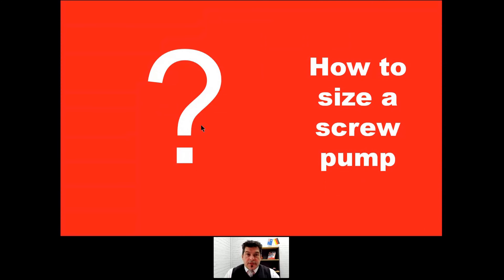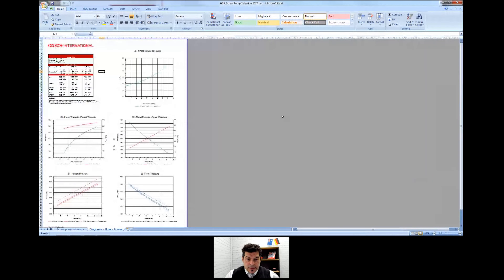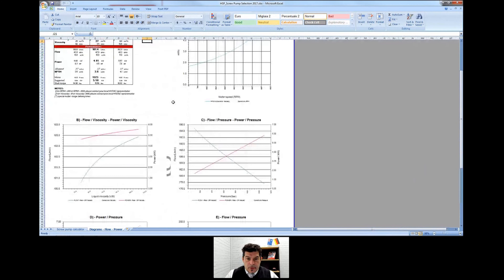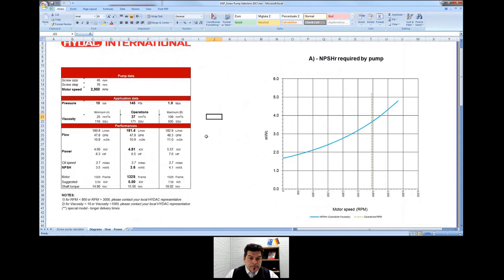How do you size it? In HYDAC, we have nice software. We give the customer a PDF with all the data characterizing the pump. The first chart — the most important one — shows the Net Positive Suction Head Required by the pump. At a given RPM, you know the Required and you make sure it doesn't conflict with the Available. In this example, we selected a 100-liter pump, which gives a requirement of 4.8 kilowatts. Since there is no 4.8 kW motor in the catalog, the next closest size is 5.5 kW — and that's what we recommend.